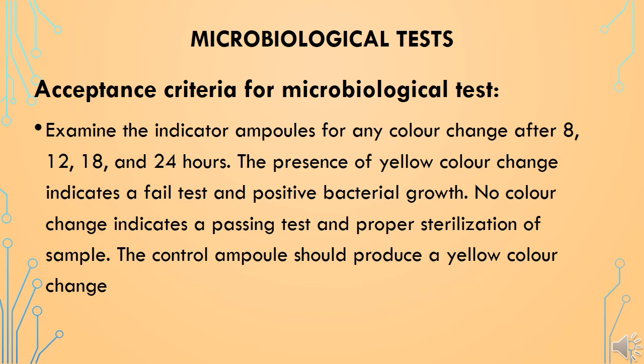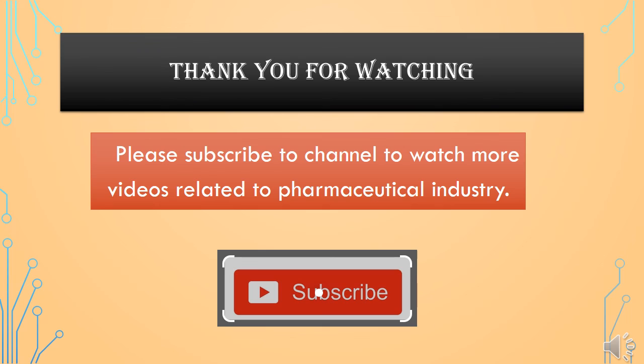Acceptance criteria for the microbiological test: examine the indicator ampoules for any color change after 8, 12, 18, and 24 hours. The presence of a yellow color change indicates a failed test and positive bacterial growth. No color change indicates a passing test and proper sterilization of the sample. The control ampoule should produce a yellow color change. These are the key qualification tests done for autoclave in the pharmaceutical industry.